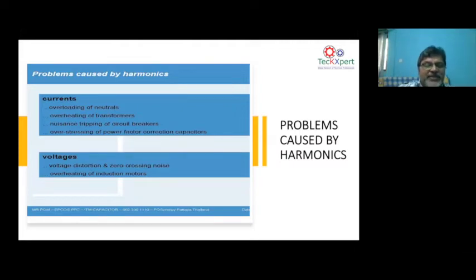These are all again mentioned as noise. Noise is a higher frequency or low frequency phenomenon above the harmonic frequencies that can be created by your LEDs or your VFDs. All this produces noise signals, and these noise signals pass over your power frequency waves and create so much disturbance on the fundamental wave. With a high-end analyzer, you can always capture and see how noise looks on a power frequency waveform. Go to the next. Your motor heating is another major issue.